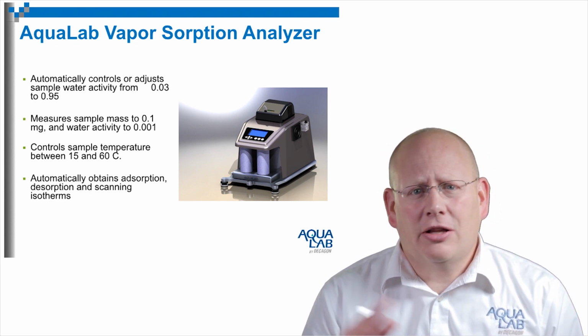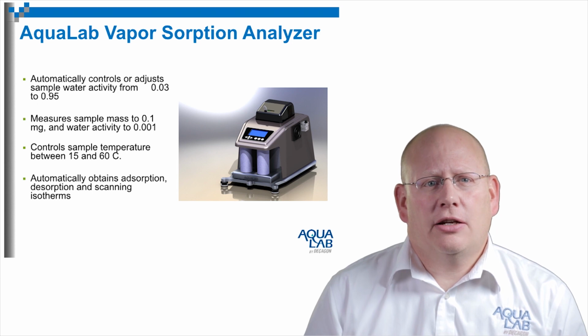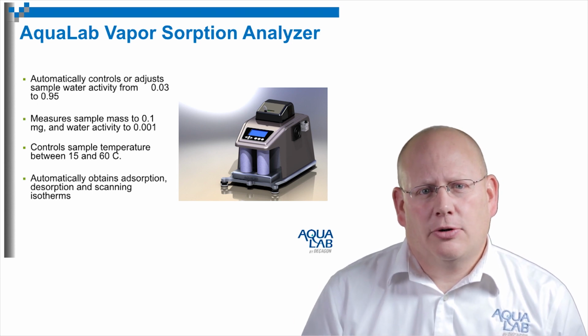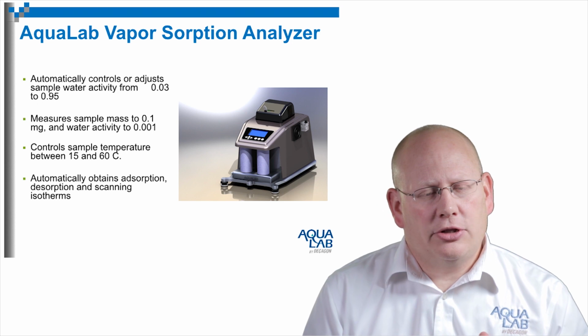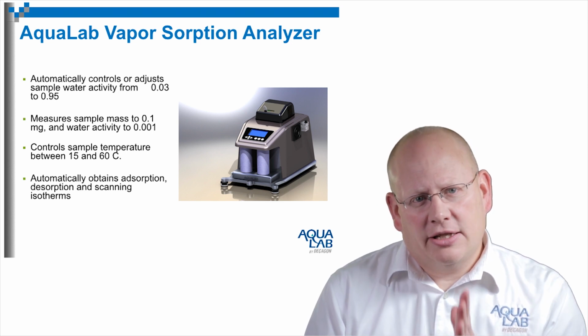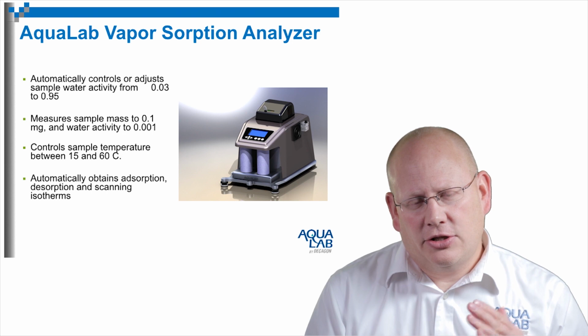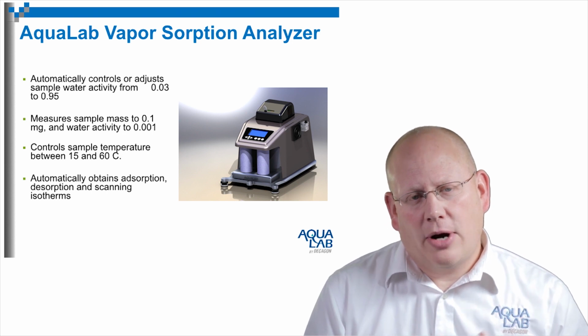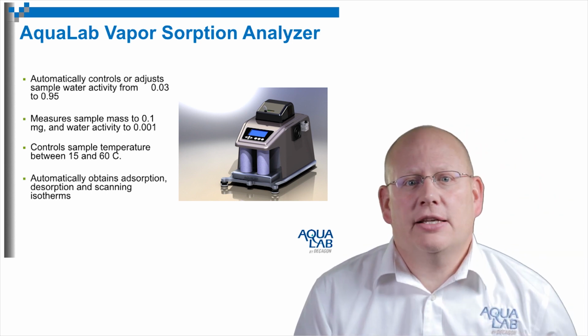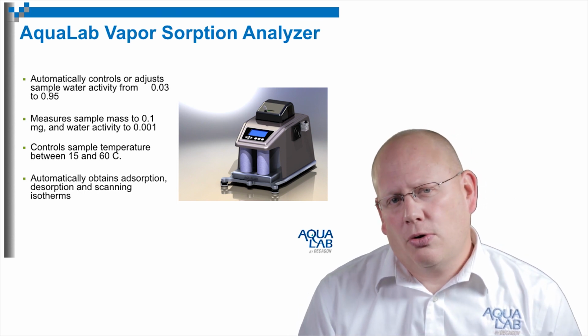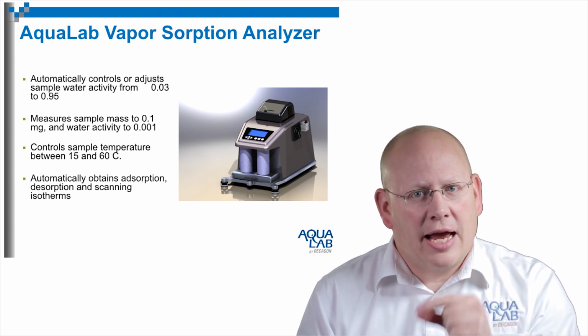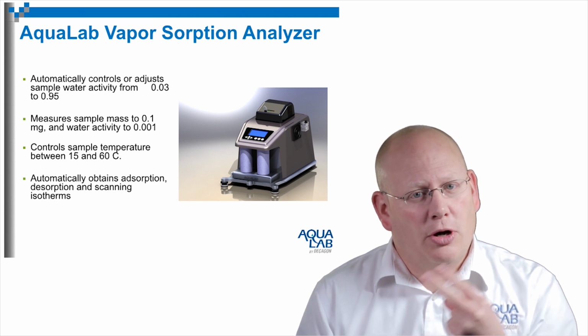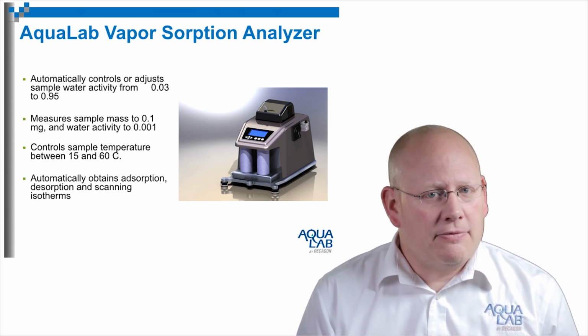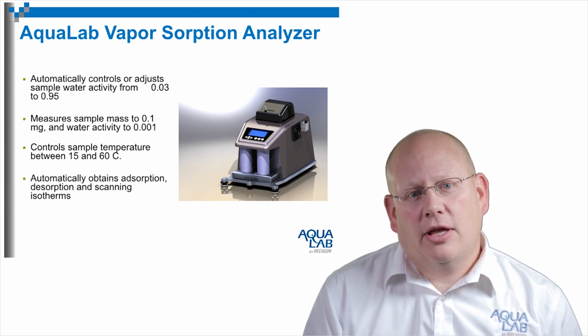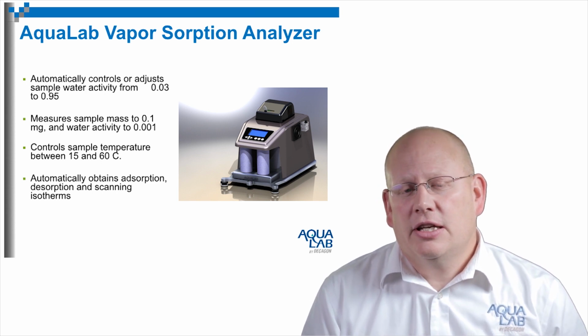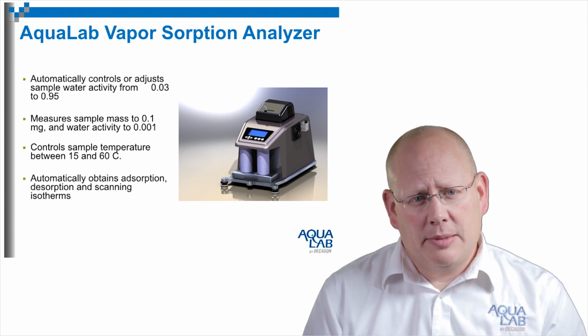But it's unique from all other types of instruments that do this work in that it can also do what's called dynamic isotherms, where instead of controlling to a specific water activity, the product is exposed to saturated or desiccated conditions, and then the changes that occur are tracked dynamically, making this a very fast process with very high data resolution. And I'll show later on the times when you would use the static and the times when you would want to use the dynamic. There are reasons to have both, and the Aqualab VSA, or Vapor Sorption Analyzer, is the only instrument that has the ability to do both types of isotherms.